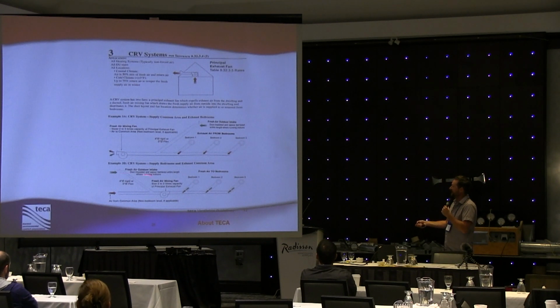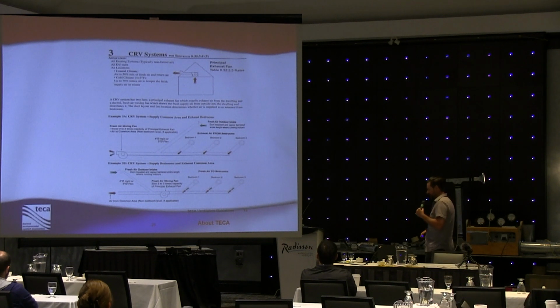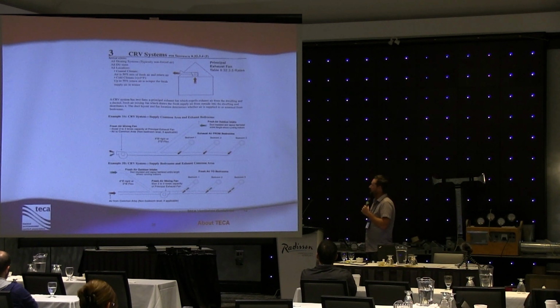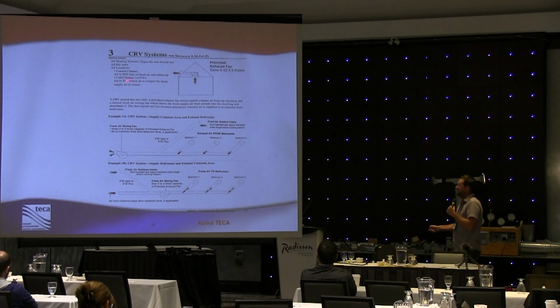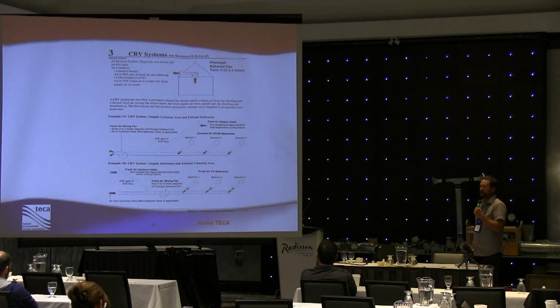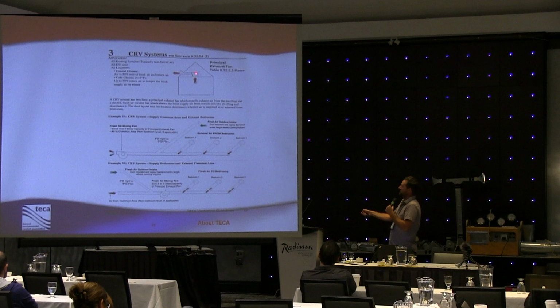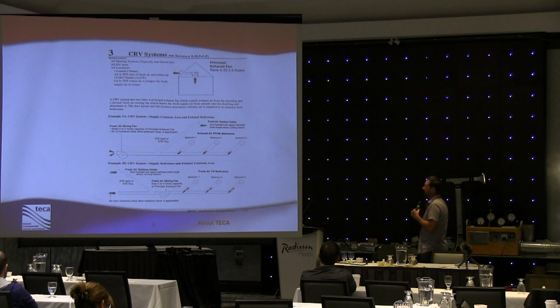Because on the coast we can take a 50-50 mix, and that's good, even on the coldest day of the year. However, when we get into cold climates where the wintertime low is less than +5 degrees Fahrenheit, we need to increase the amount of interior air that we blend with that fresh air from the outside. The way we do that is we use a larger mixing fan. In those cold climates, this mixing fan would have to be 3 times the size of our principal exhauster. So if this was 100 CFM, if that's what the code prescribed, this fresh air mixing fan would have to be 300 CFM.